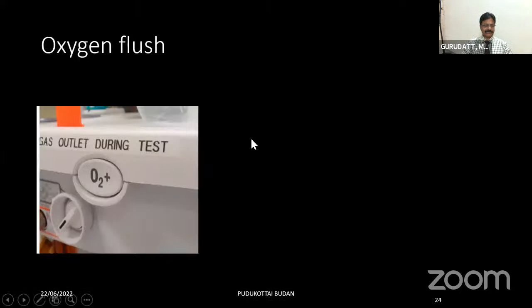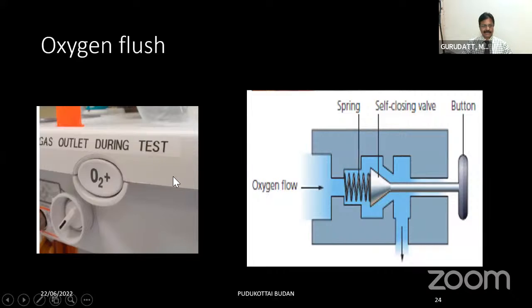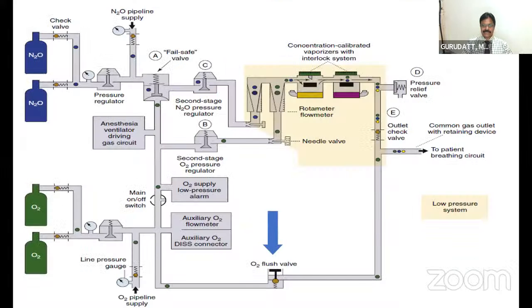Coming to another component, that is the oxygen flush. You should recognize the oxygen flush here by O2 plus. That is how you can easily recognize it. As soon as you press this button, 35 to 70 liters of oxygen will start flowing out of the common gas outlet. One thing you should also remember is that this oxygen flush valve is directly connected to the pipeline source, or if you have cylinders, directly to the pressure regulator. That means the pressure is the same as the pressure of the pipeline system or the pressure regulator, that is 45 psig or 60 psig. The oxygen will flow through the flush valve once you activate it.